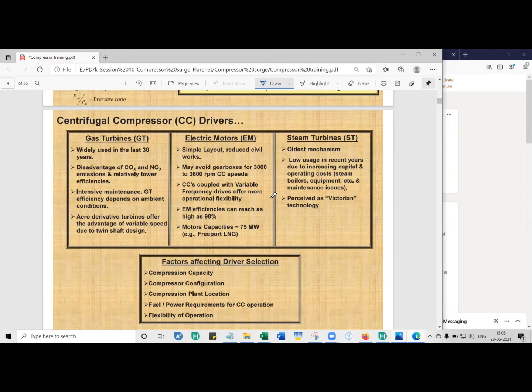Let's say you took the gas turbine and installed it in some place which is well above mean sea level, 200 meters above in some part of the world. As you keep going higher and higher, the air becomes thin, the air density keeps reducing. Again, the power output decreases. So there are certain disadvantages with gas turbines.